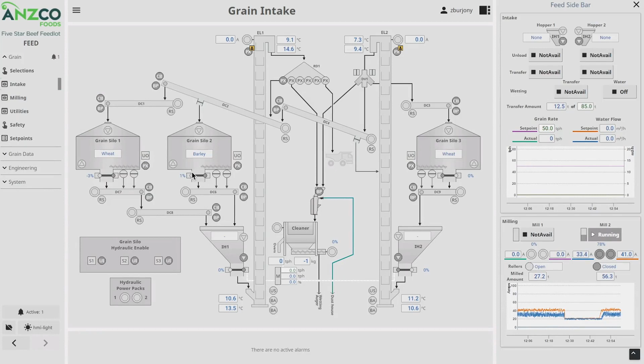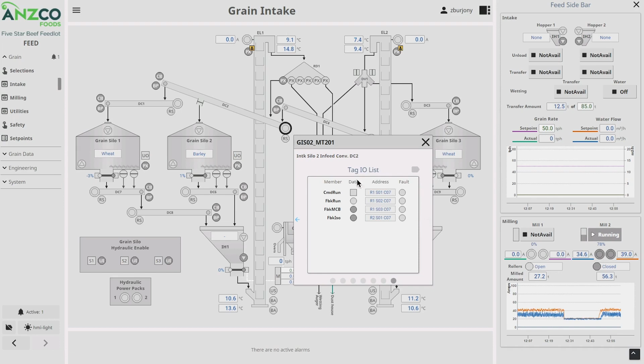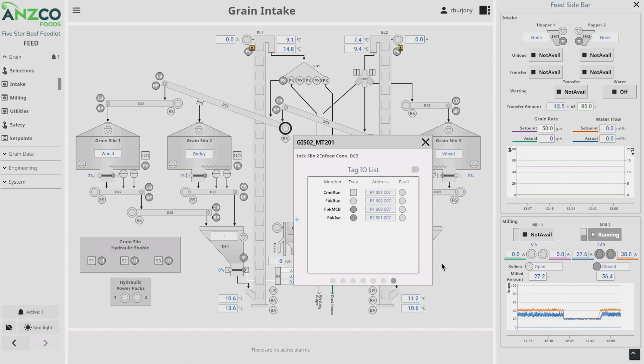Pop-ups are used to display critical information, including monitoring and control. For example, a motor, we have all the actions that we need on the first page. Then we've used the carousel view to scroll across to get further information about this device, including trend for that device, any tag alarms, any tag actions taken by operators, as well as tag parameters such as the area and the tag name in the PLC, and also the wiring of all the I/O connections for that device. So for example, this motor, we have an output, some feedbacks and an isolator, and we can see where they're wired and the live values from the PLC.